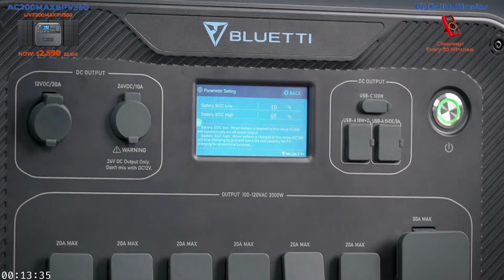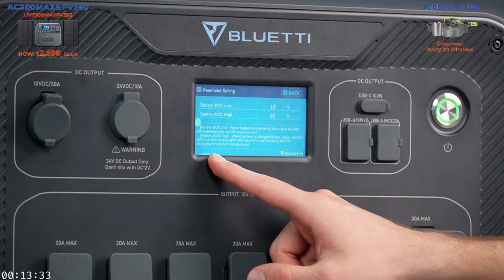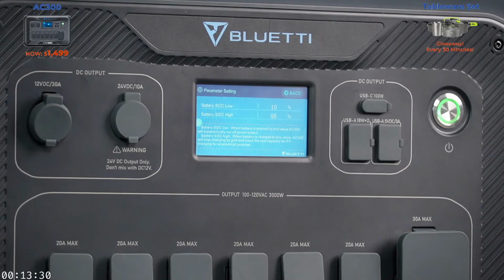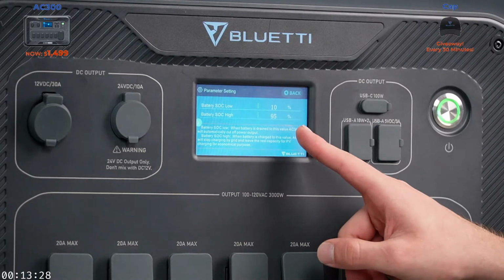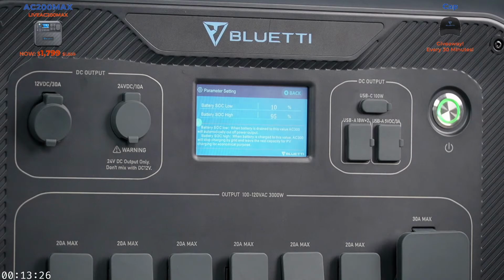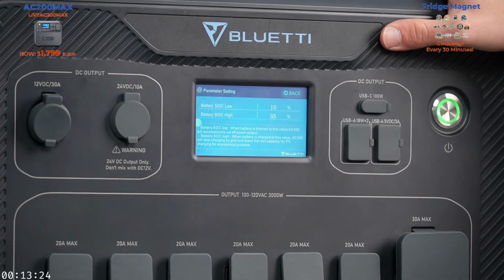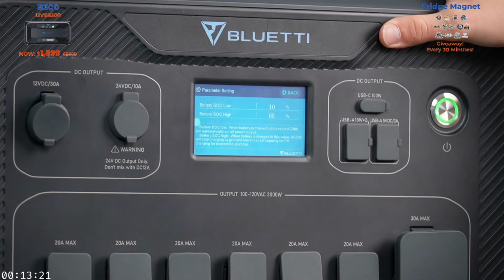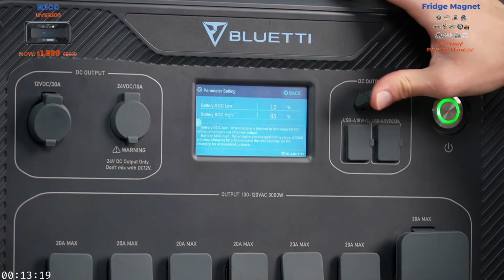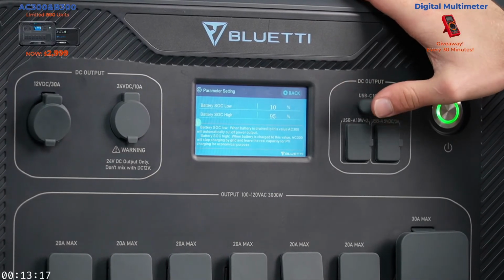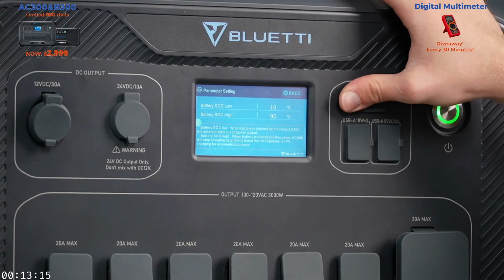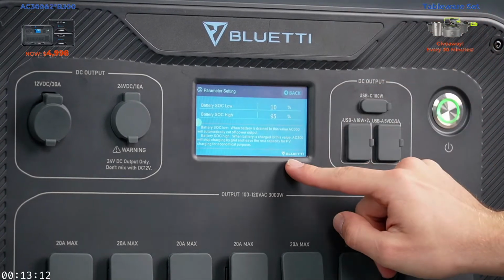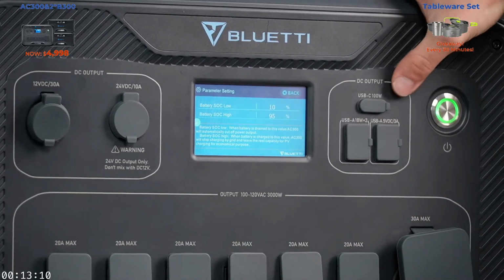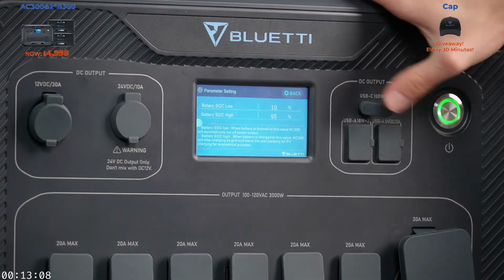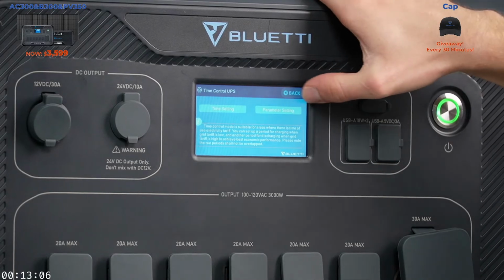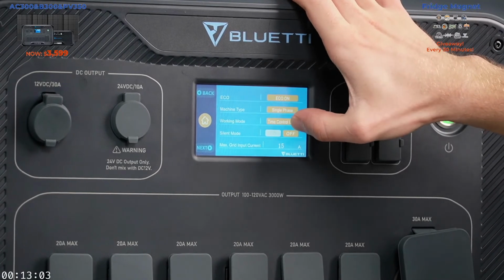Here's the parameter settings, and we have an explanation right here. Battery SOC low: when battery is drained to this value, something like maybe 10%, AC300 will automatically cut off power output. Battery SOC high: when battery is charged to this value, AC300 will stop charging by grid and leave the rest capacity for PV charging, for economical purposes.